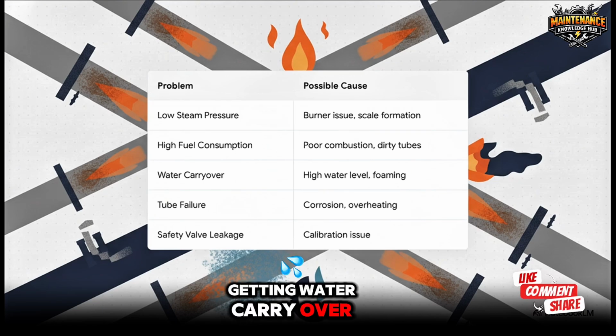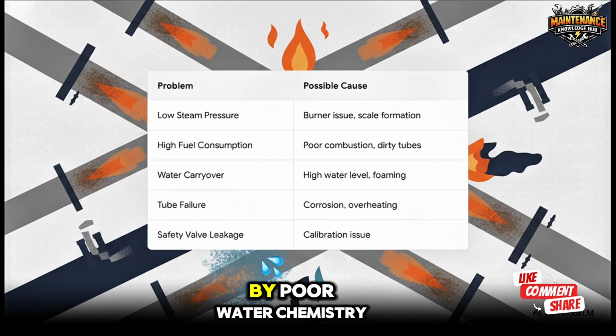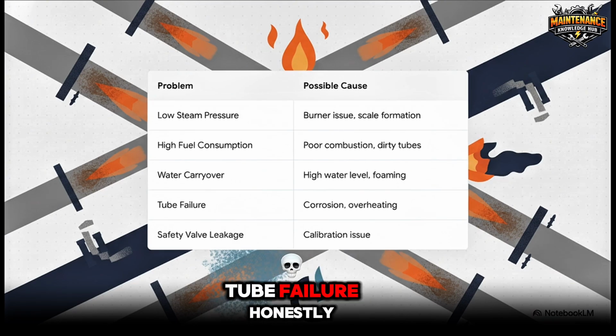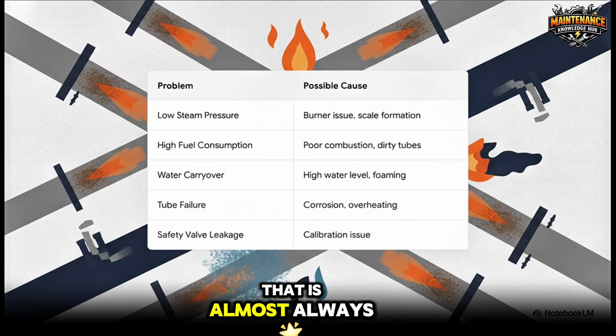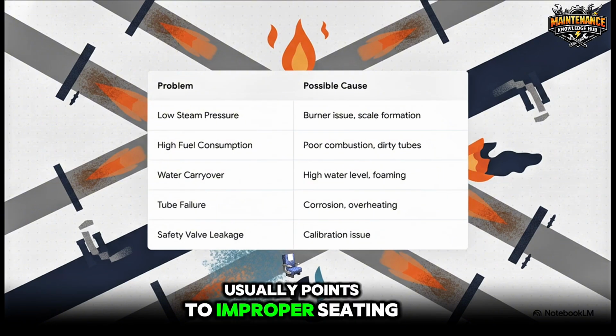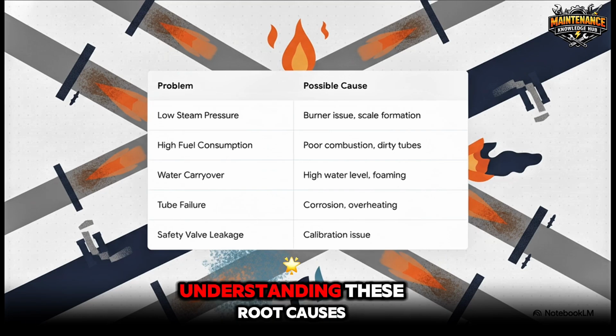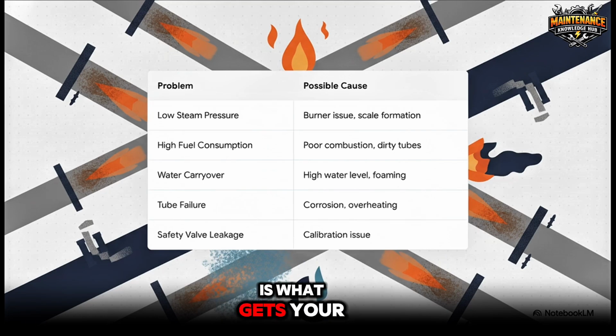Getting water carryover into your steam lines? You probably have a high water level, or maybe foaming caused by poor water chemistry. Tube failure? Honestly, that is almost always a direct symptom of unchecked corrosion or localized overheating due to scale buildup. And safety valve leakage usually points to improper seating or a calibration issue. Understanding these root causes is what gets your system back online faster.